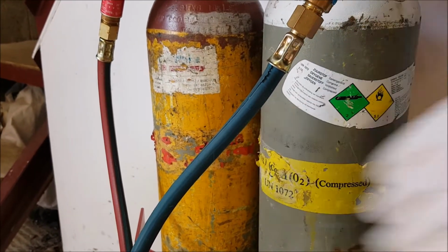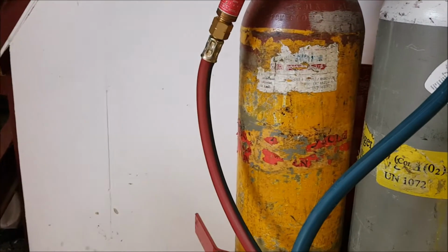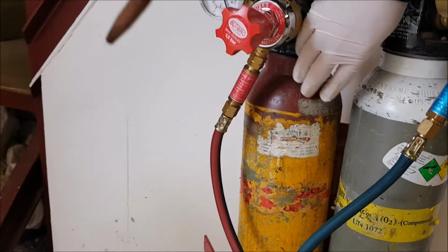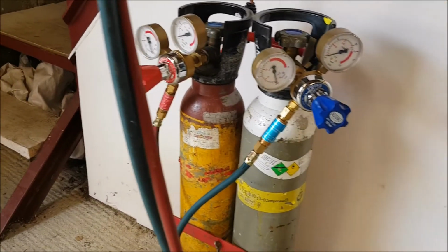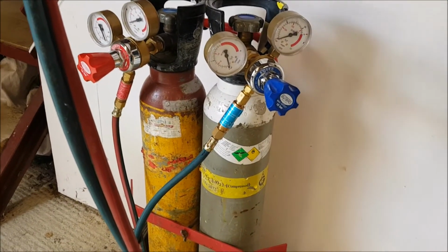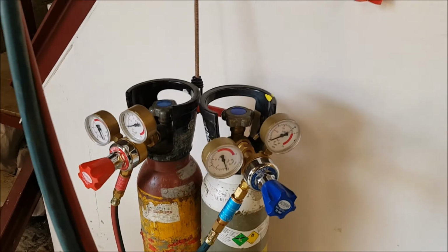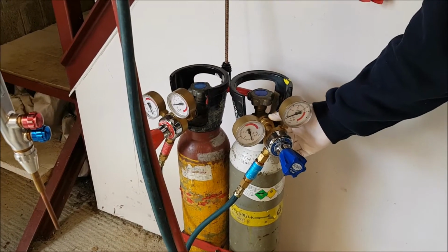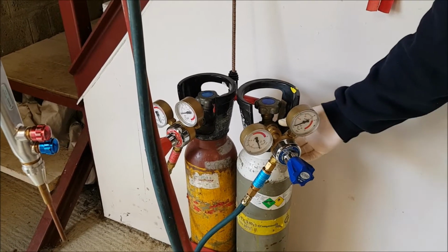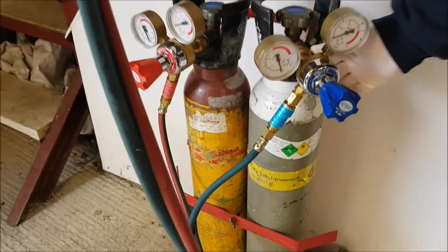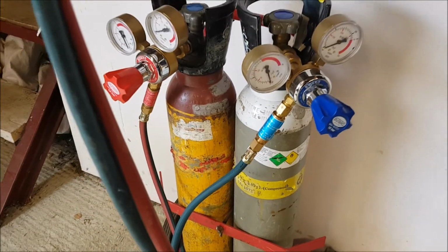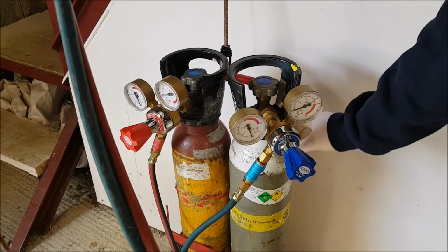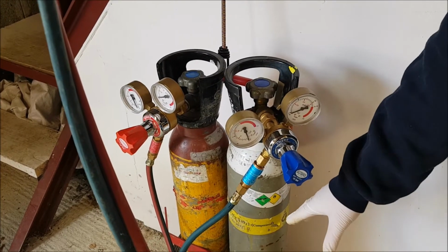You can see a yellow bottle here with a kind of burnt orange or red cap on it, and that red cap indicates that it's acetylene. So this is acetylene, this is oxygen, this is for brazing purposes. Again, I went through it in the brazing video, but I can't emphasize enough the danger. This regulator here has the same thread as my nitrogen regulator, so I could quite easily put a nitrogen regulator onto this bottle and mistakenly put oxygen in if I'm not careful. So watch your labels. It's a white cap, doesn't matter about the color of the bottle, it's the white cap and it's labeled, so make sure you read the label.